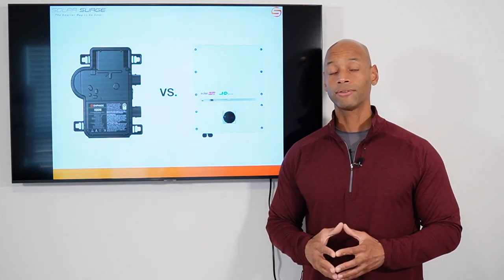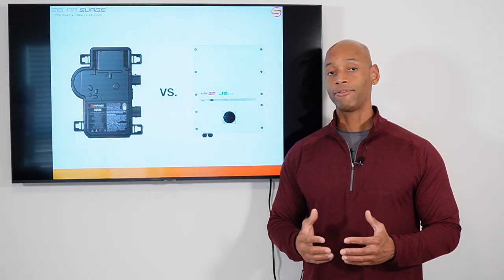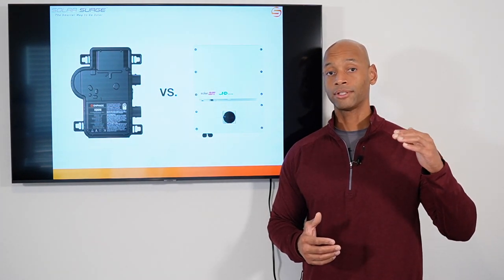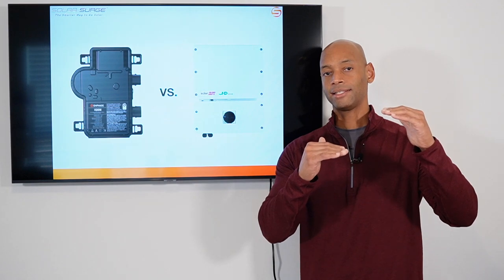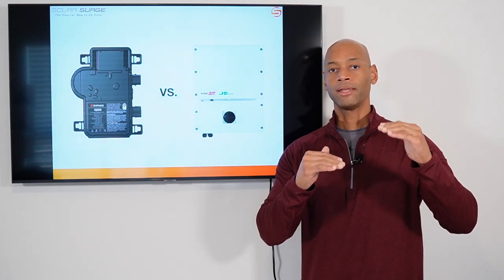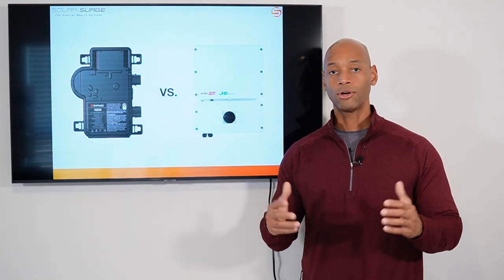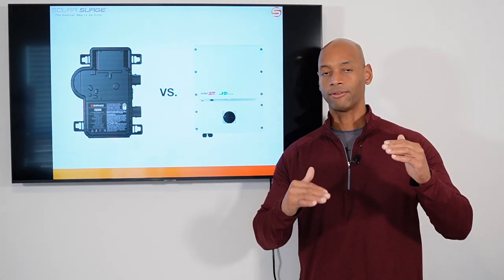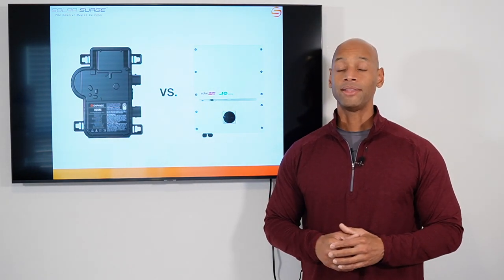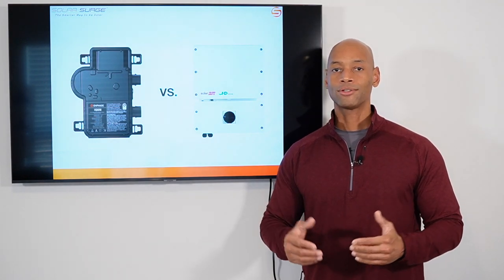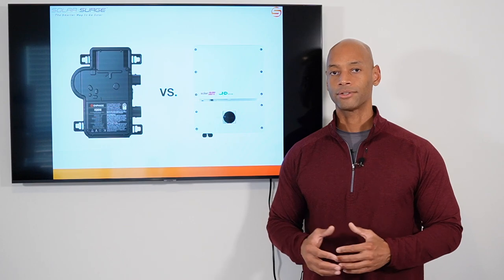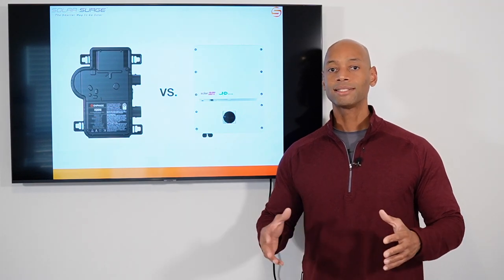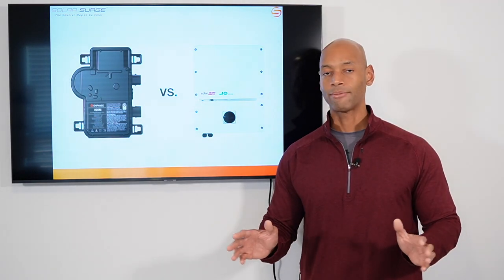But it's very common in the solar industry to have your DC rating on your solar panels as much as 20 or 25% higher than the AC rating on your inverter. And so you know you might ask, Joe, why would you put a larger solar panel on an inverter that can't handle it? And the answer is very simply the way that solar panels are rated are in what's called STC conditions or standard test conditions. Basically that means perfect laboratory conditions.